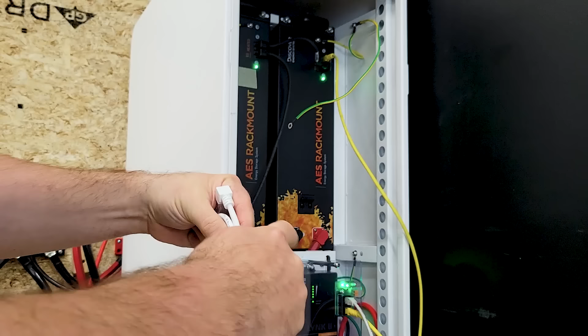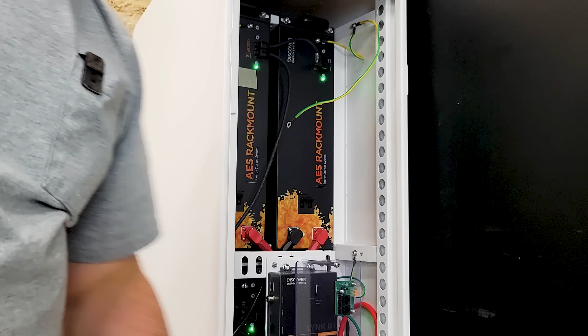This is currently on, so we'll see if we can do a hot swap. There we go, one cable from the switch to the link. Again, the link communication device isn't necessary for operation of the battery - you could set this system up with voltage only. But if you have the ability to do closed loop communication, it's a bit nicer to do that.